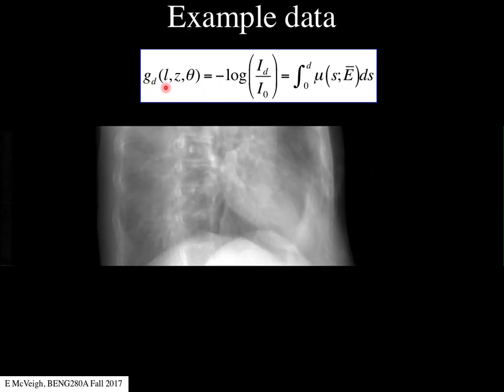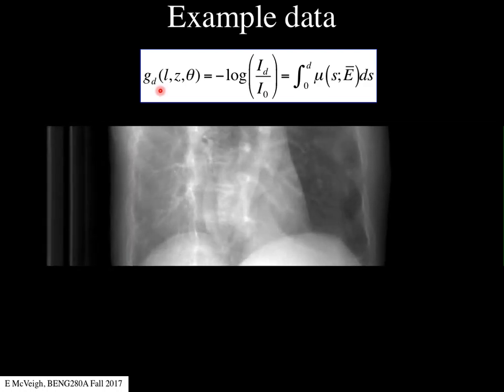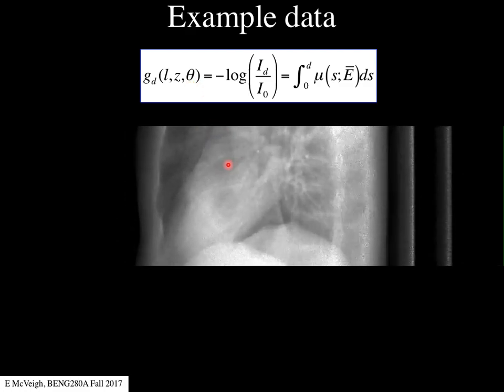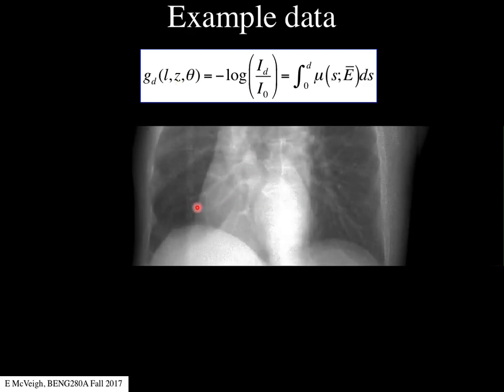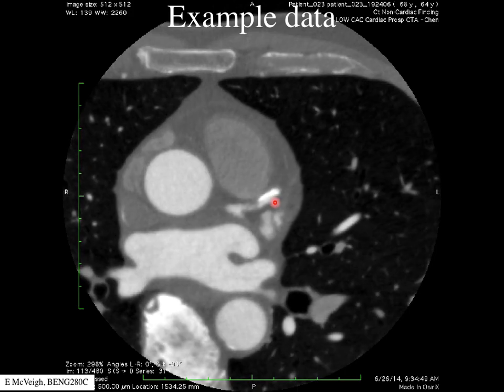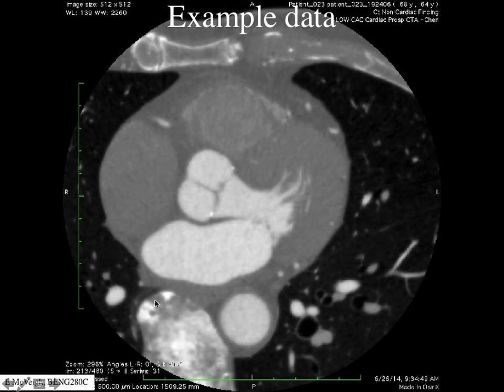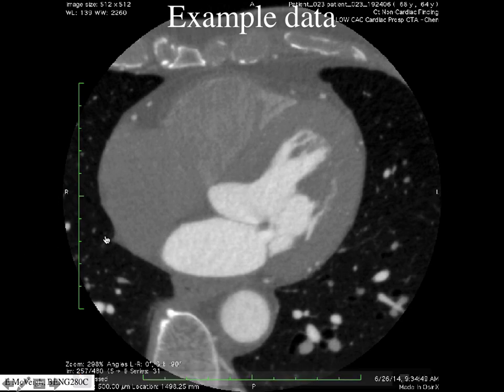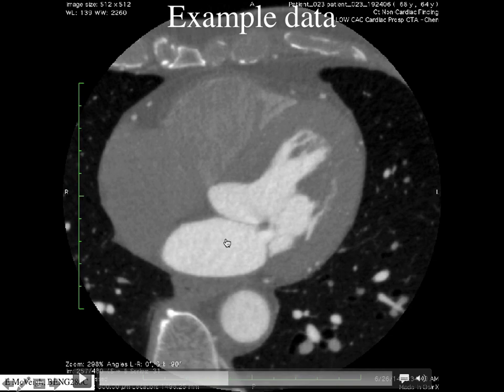Here's our parameterization. G is the brightness or the amount of attenuation, proportional to L — the L direction. This is the z direction, and you can see the theta's clicking around. We'll set z to zero so we're along the central row. When we look at the two-dimensional data achieved using this, we get a picture where the source for one projection comes through, this is the L direction as we're detecting, the z direction is a fixed slice, and we get about 800 thetas or views of this plane. In two dimensions, this is usually x and y, and z is through the plane.